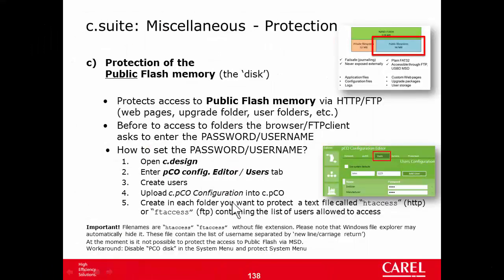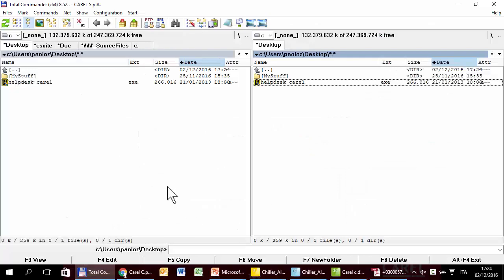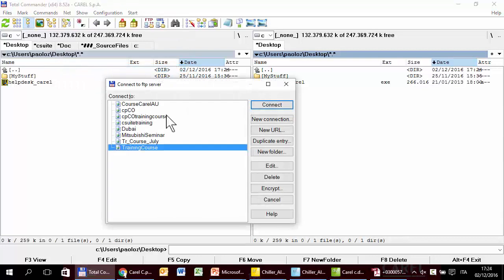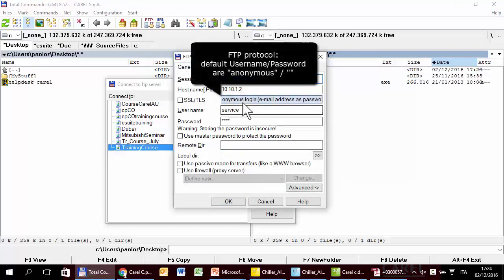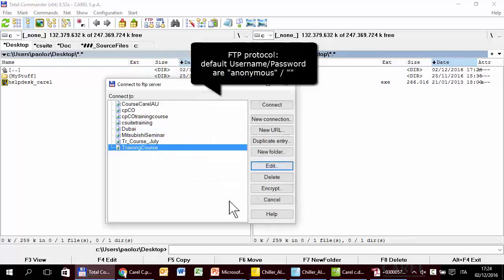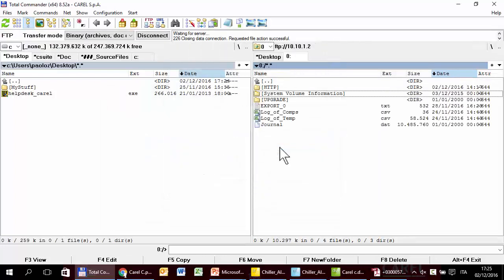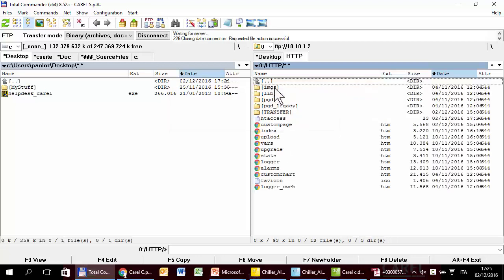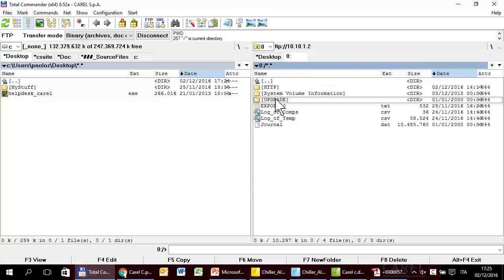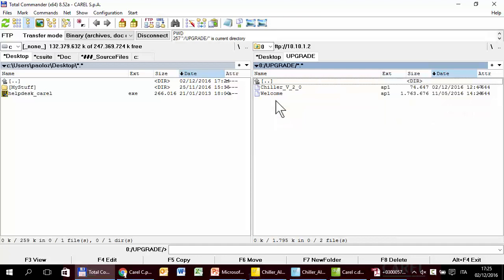Now we can try the second feature: protect access via FTP. So I have to create a file called ftaccess in the folder we want to protect. Without protection I can connect without a password — here is the content of the memory and I can enter everywhere. Let's suppose we want to protect the upgrade folder to prevent someone from copying a competitor project there. So I have to copy a file called ftaccess into that folder.